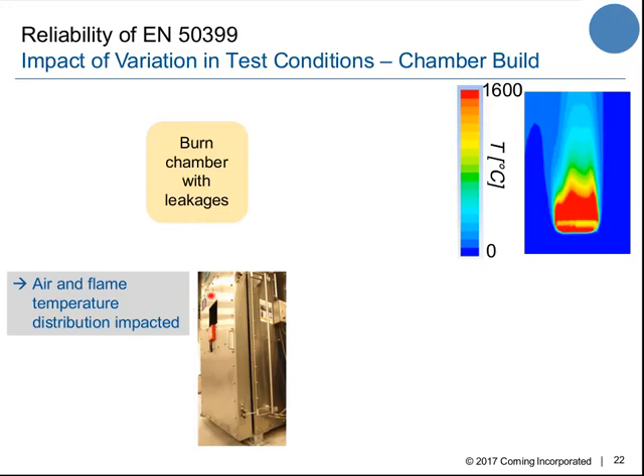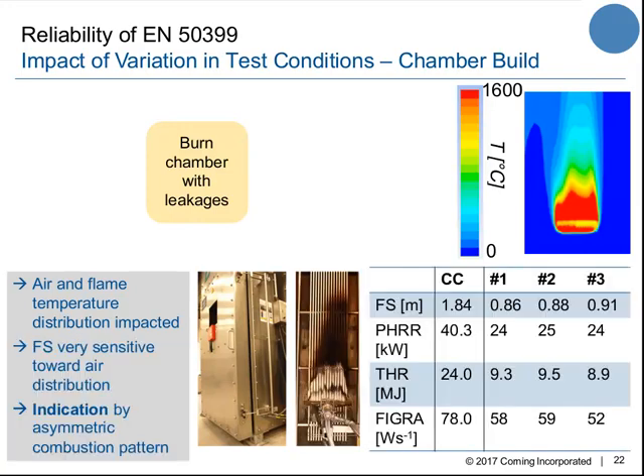What you see here is now the burn chamber as it is here in Berlin. We closed this burn chamber, but we left a small gap of 10 millimeters in the door. Then we tested again our calibration cable, just under normal conditions. What we found is the following: the flame spread is half of what we got before, just based on this gap. And we also saw this asymmetric combustion pattern, which was in pretty good match with what we simulated from the temperature distribution of the flame. So this asymmetric combustion pattern seems to be a very good indicator that the air distribution in this chamber has changed.